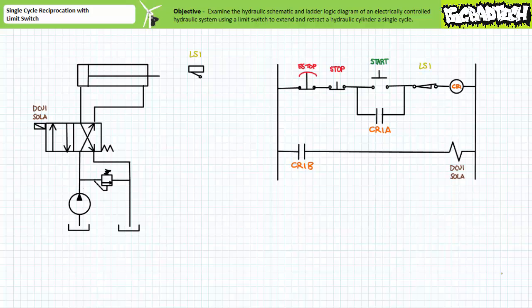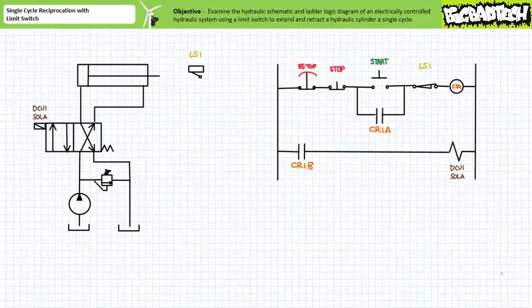At either the limits of extension or retraction, flow will cease and pressure will rise to the set point of the pressure relief valve. In this system's deactivated state we would expect the cylinder to be retracted. The physical limit of extension is a limit switch LS1, which when the tip of the rod contacts it will change to its opposite electrical state. Given there are components interfacing the electrical, mechanical, and hydraulic realms of our circuit, we should expect to see at a very minimum the solenoid DCV1 Sol A and the limit switch LS1 in our ladder logic diagram.